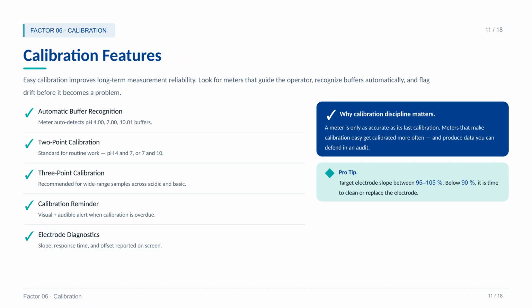Factor 6. Calibration features. Easy calibration improves long-term reliability. Look for automatic buffer recognition, 2-point and 3-point calibration options, calibration reminders, and electrode diagnostics that report slope and response time. A meter is only as accurate as its last calibration. Meters that make calibration easy get calibrated more often and produce data you can actually defend in an audit. Target an electrode slope between 95 and 105%.